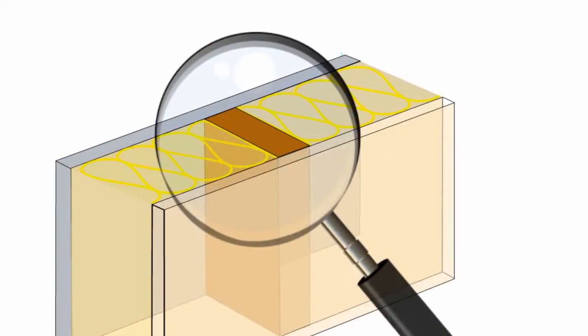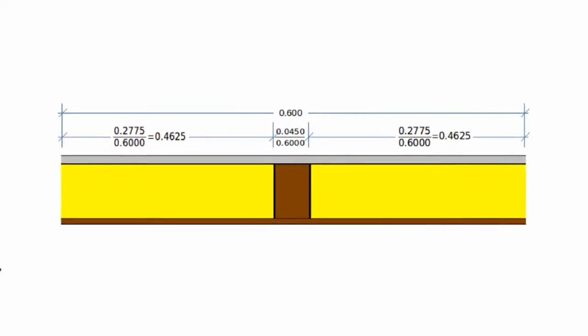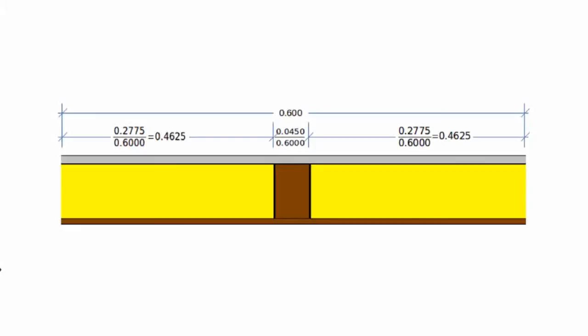Let's have a closer look at the stud. The distorted isotherms are indicating that there's a thermal bridge and also that the effects of the thermal bridge are not confined to the stud area itself. Purely area weighting the materials in the layer would not account for the thermal bridging effect accurately. So how do we do this?